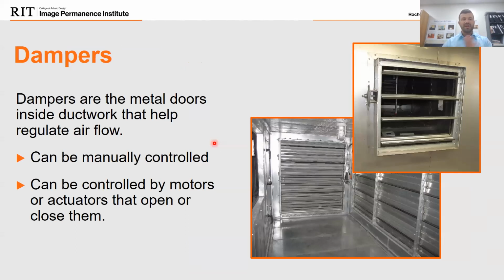They're going to regulate airflow. So the dampers can open or close to block the airflow or allow air to move. On some older air handling units, your dampers are going to be manually controlled. That means someone actually has to walk up and adjust the dampers manually through an adjusting arm on the dampers. On most of the newer units, the dampers are controlled by motors or actuators that can open or close them in response to need or demand, or even if you just choose you want to close off a room for a little bit, you can now control those through dampers.